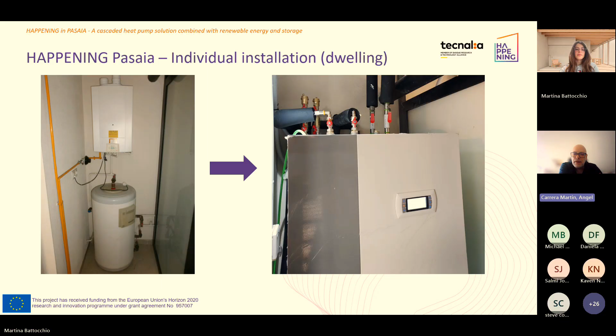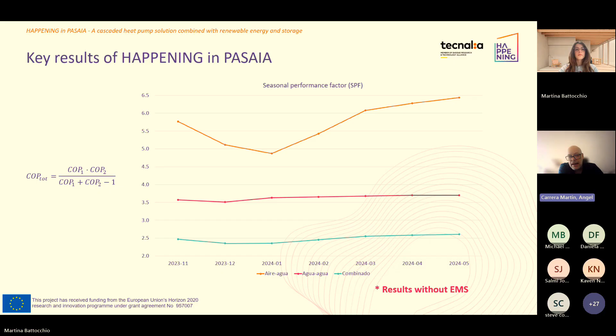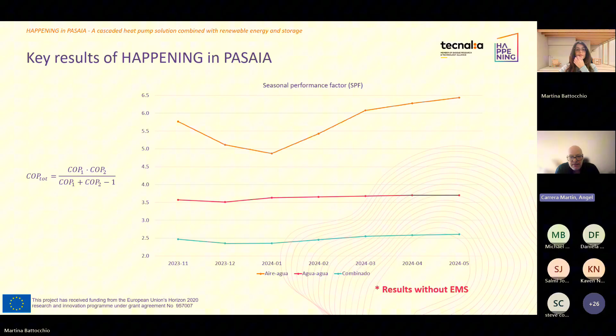Well, then we were able to have some monitoring data of the system during like 6 months, well, now a bit more. And here you can see what is the performance of the system as measured during this period from November 2023 to May 2024. The air to water heat pumps have a seasonal performance factor of around between 5 and 6, I would say, depending on the temperatures, which is quite high. And the individual heat pumps are running at 3.5 and growing slightly. There are some tweaks we were able to make in the control to improve the performance a little. So the overall COP of the system is something at around 2.6, which is quite good, I believe, for a cascade system. Next, please.